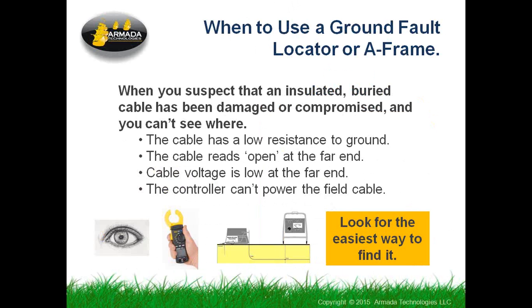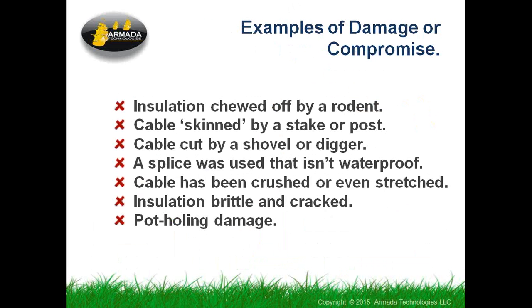You can also test for an open. When you're doing this kind of testing, you lift both ends of the cable from any connections that are there. You can short circuit one end of the cable and go to the other end and test it with a meter, and if it shows open, you've got an open cable somewhere in between. These are all just ways of verifying that it's worth the time and trouble to try to figure out if that's what's going on with you. Use the easiest way to find it that you can. That means using an AC clamp meter, using your Mark I eyeball, or using a ground fault locator. All of these things can lead you to the trouble.